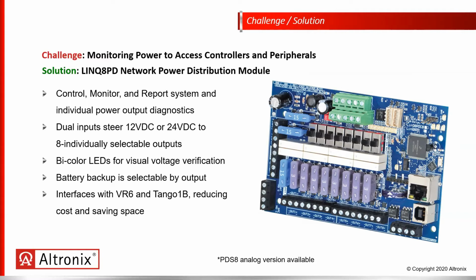The Link 8 PD is also capable of being used with and stacked on top of a voltage regulator, our VR6 product. So now, minus the 8-pin connector, we have the ability to take our 24 volts DC in and then leverage the 12 volts DC out, as well as 24 volts DC to our Link 8 PD, again, giving us that ability to individually select 12 or 24 volts DC per output, even from a single 24 volts DC power source.